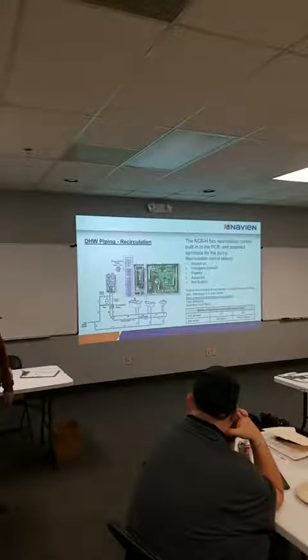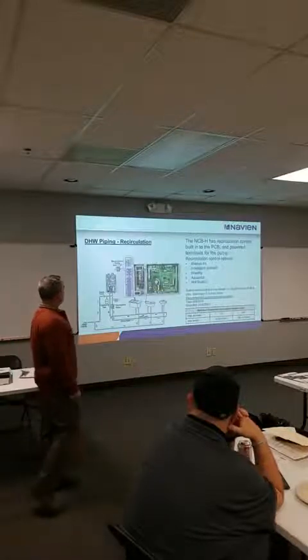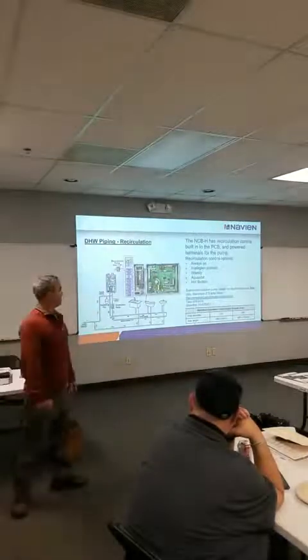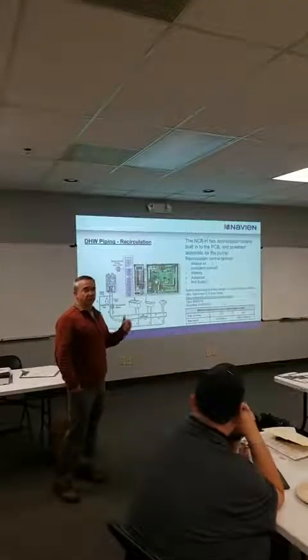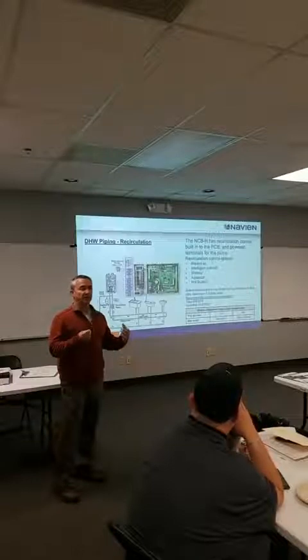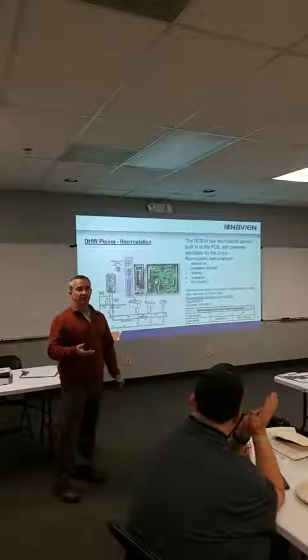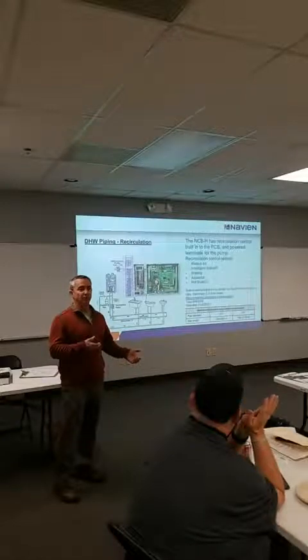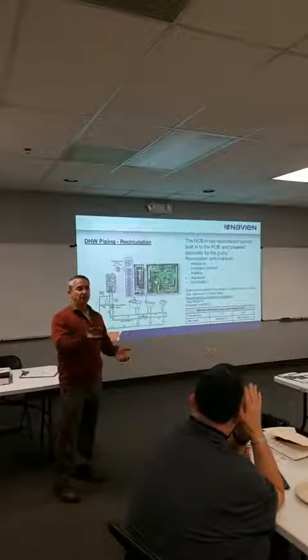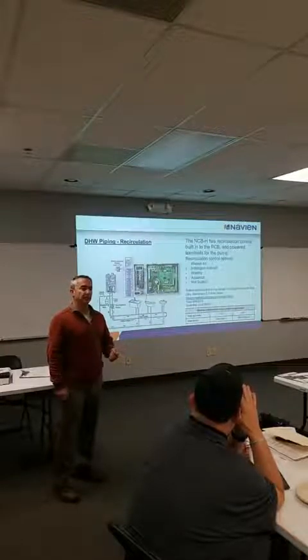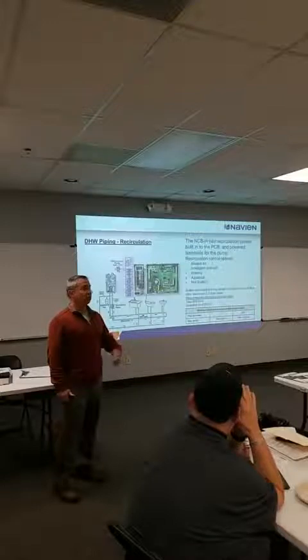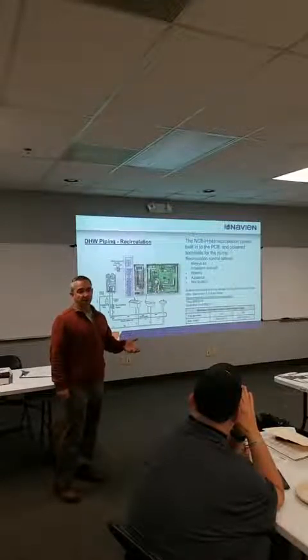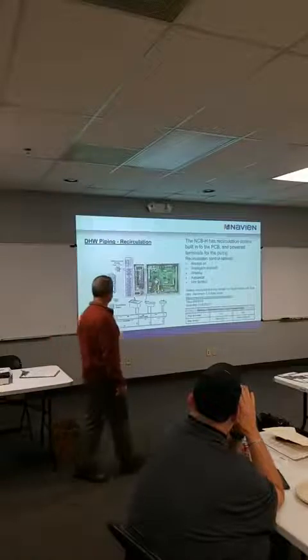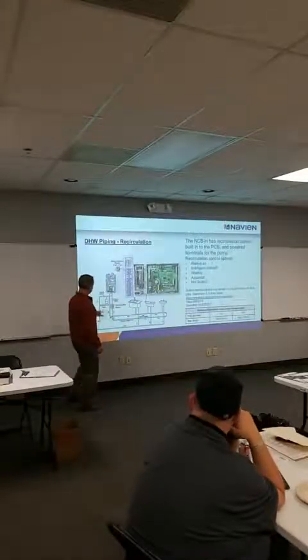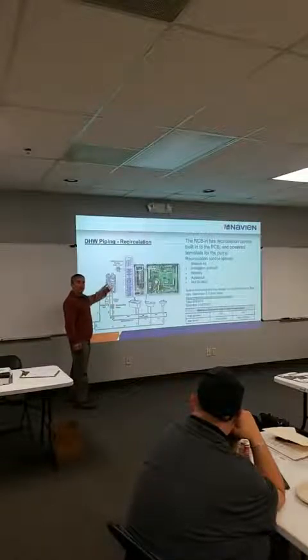What controls that recirc pump? Is it doing it off line temp or timer? Yeah, there's a number of different options. We can do internal temperature sensing. So we're looking at incoming temp and set point, and when the incoming temp drops to below, I think, 18 degrees of set point, it'll fire the unit. And then when it sees a 9-degree differential coming back, it shuts down. And it'll do that on a 24-hour cycle, or you can program in a 1 day, a 3 day, or a 7-day cycle. You could also, if you want, hook an external aquastat somewhere out and wire that back, and you can control it off a line temperature in the field somewhere if you want.